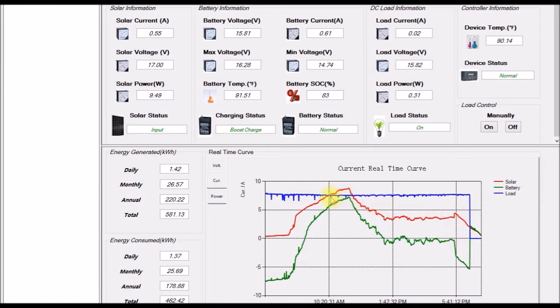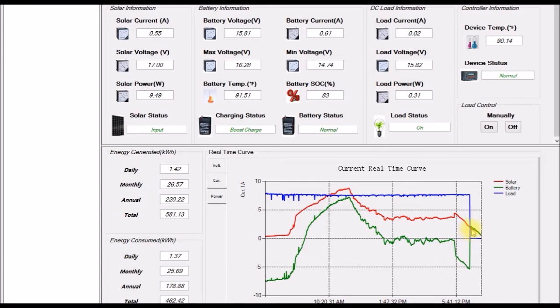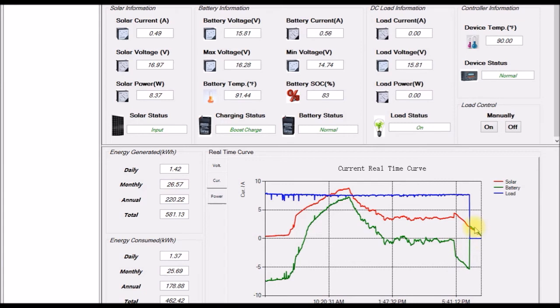If you look here at the solar current, if I were to continue this red line up and over and down that would be peak power or current out of the solar panels if you just filled in that curve. Here it started dropping off to the point that the battery was being discharged because the solar panels couldn't keep up with the load, and then about here is when the load shuts off and then the solar charge controller tries to recharge the battery again. So it's gone from float charge back to boost charge here.